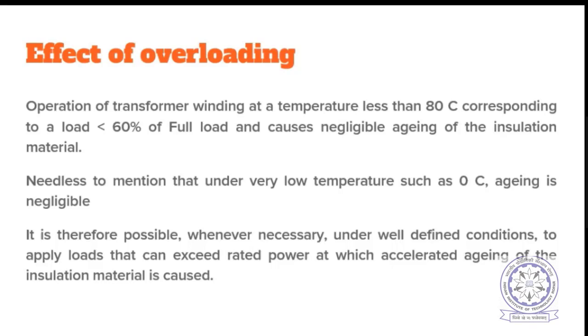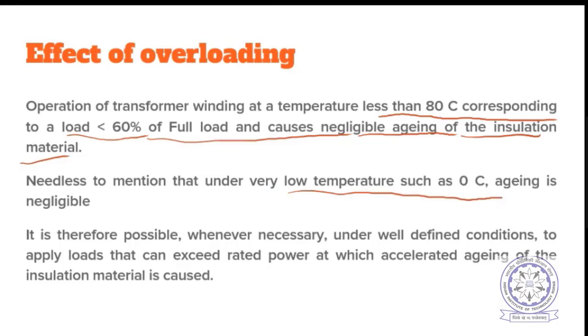Operation of transformer winding at a temperature less than 80 degrees centigrade. So 80 degrees centigrade actually corresponds to 60% of the full load. Less than 80 degrees centigrade, which corresponds to 60% of full load, causes negligible aging of the insulation material. This is the observation from the investigations. Below 80 degrees centigrade, no significant aging is observed. And needless to mention, at very low temperatures such as 0 degree centigrade, aging is completely negligible.